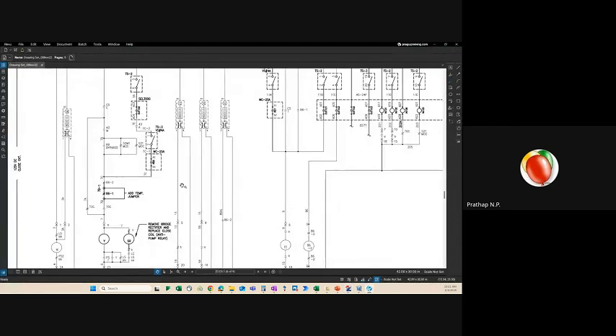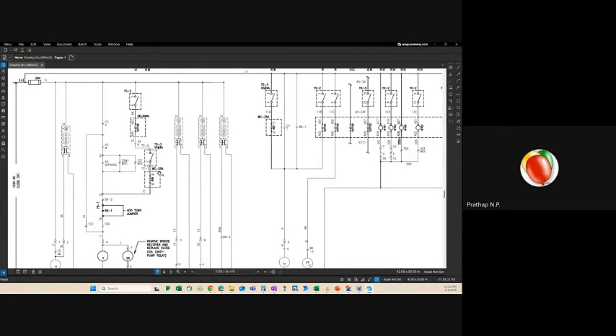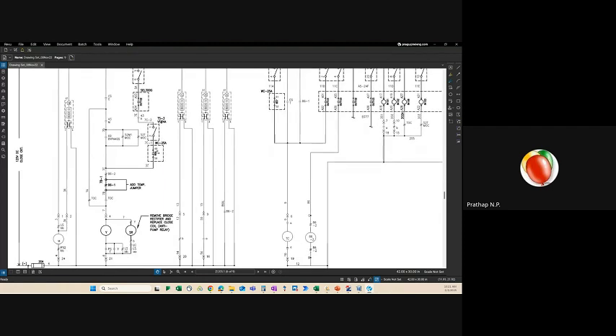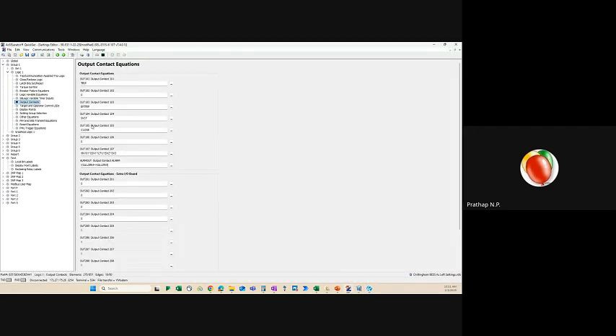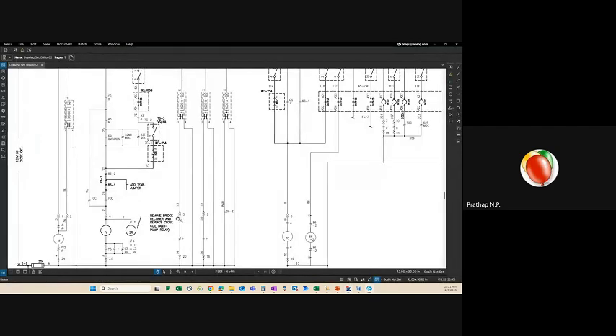Going back here, let's say this switch is closed, it's a small test switch, and the customer's relay wants to close. But if this is open, your breaker will not close. So in order for the breaker to close, this contact should also close, and this contact should also close. Now, what usually they would do is, so what was that contact? Sorry, I'm jumping.